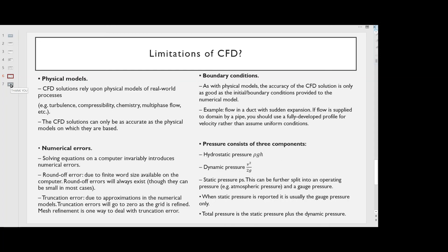Boundary Conditions — the accuracy of the CFD solution is only as good as the initial and boundary conditions provided to the numerical model. For example, for flow in a duct with sudden expansion, if flow is supplied to the domain by a pipe, you should use a fully developed profile for velocity rather than assume uniform conditions. Pressure consists of three components: hydrostatic pressure (ρgh), dynamic pressure (v²/2g), and static pressure (p_s). This can be further split into operating pressure, e.g. atmospheric pressure, and gauge pressure. When static pressure is reported it is usually the gauge pressure only. Total pressure is the static pressure plus the dynamic pressure.